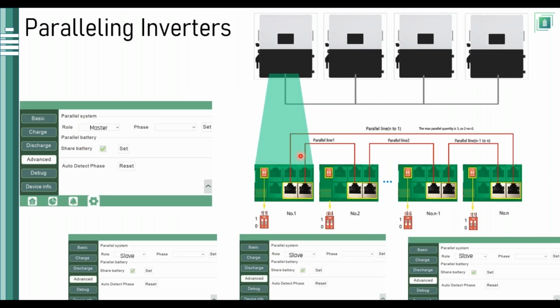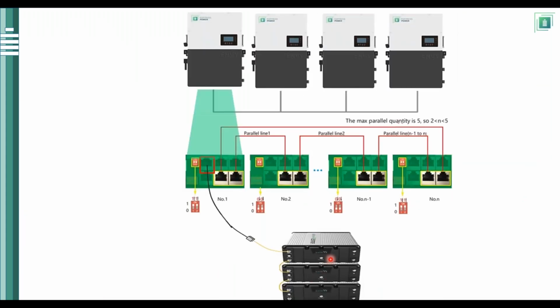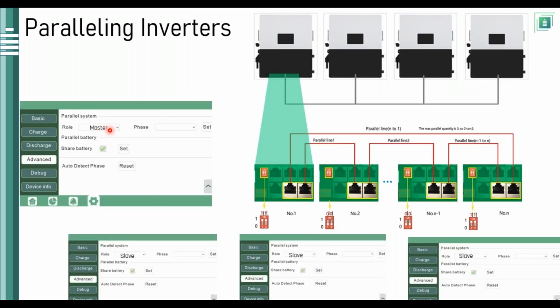And once you do that, all you do is go on the LCD screen. You're going to go on the settings of the inverter. You're going to go on advanced, and then you're going to scroll down and assign the role to each inverter. As we stipulated here, you're going to assign master to the first inverter. The first inverter, or the master inverter, is always going to be the inverter that communicates directly to the batteries. So we're going to assign master to the first inverter, and then the rest will be assigned as slave.